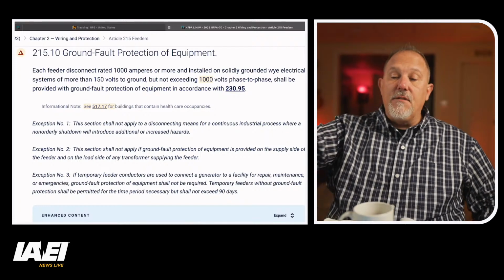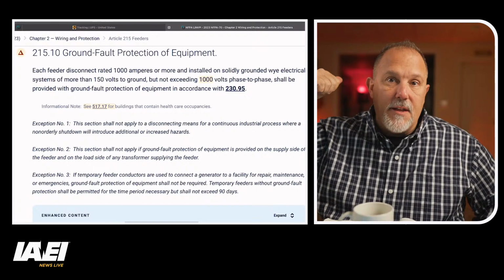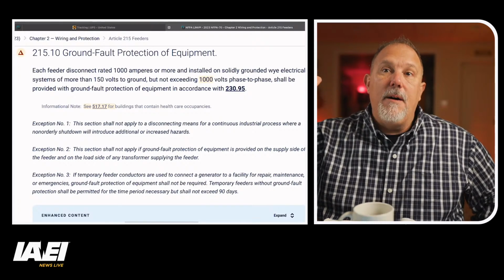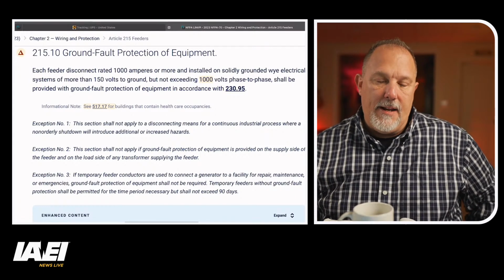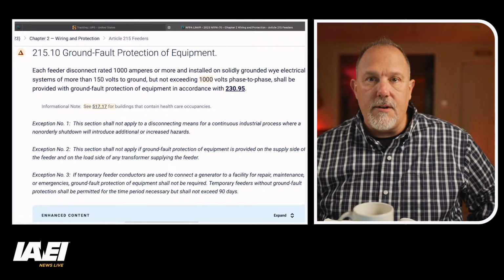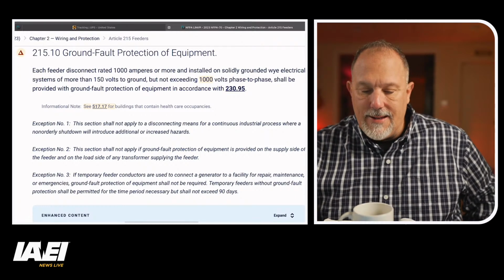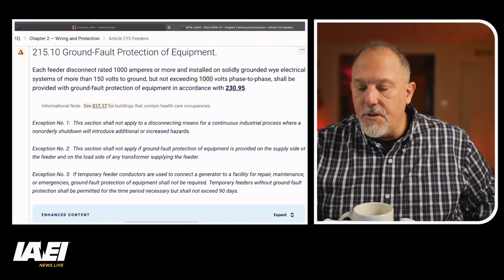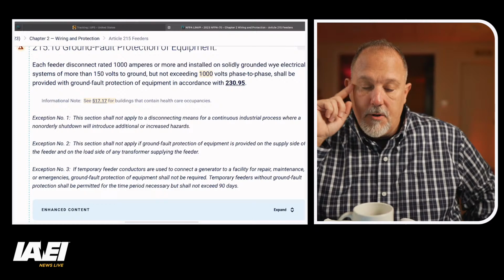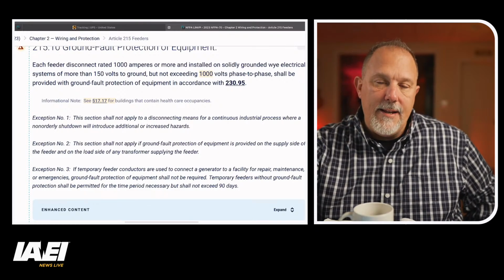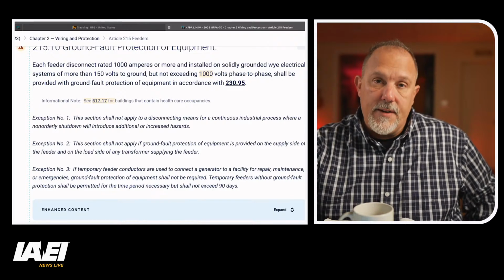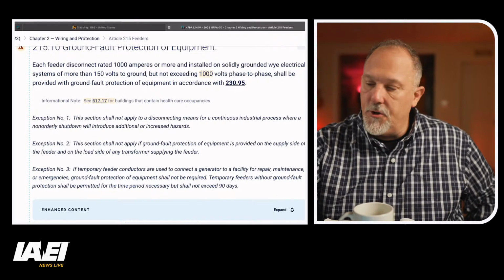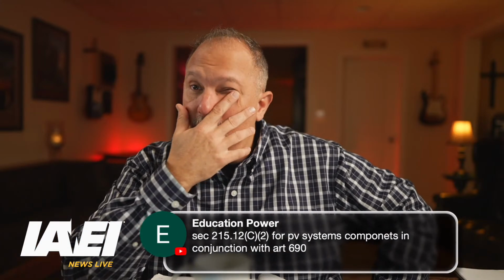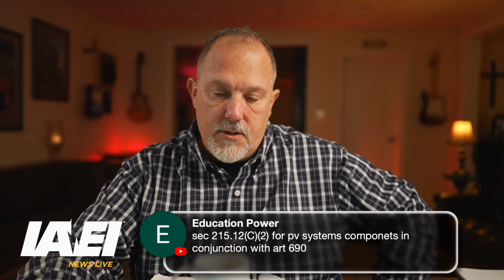So if I have a feeder that's 1,000 amps, I probably have a service device with a higher ampere rating, and that's going to be required to have GFPE per 230.95, so I wouldn't put it here for 215.10. And then it says, if temporary feeder conductors are used to connect a generator to a facility for repair, maintenance, emergencies, and so on, you have a 90-day grace period while you're doing the work. Don't ask me where the 90 days came from. So that's what that's all about. Robert says, see 215.12(C)(2), 215.12.